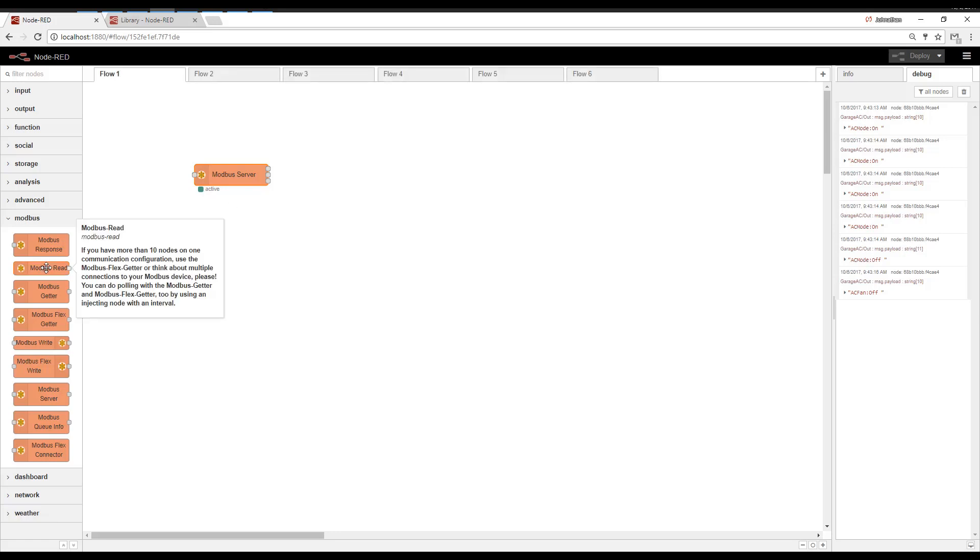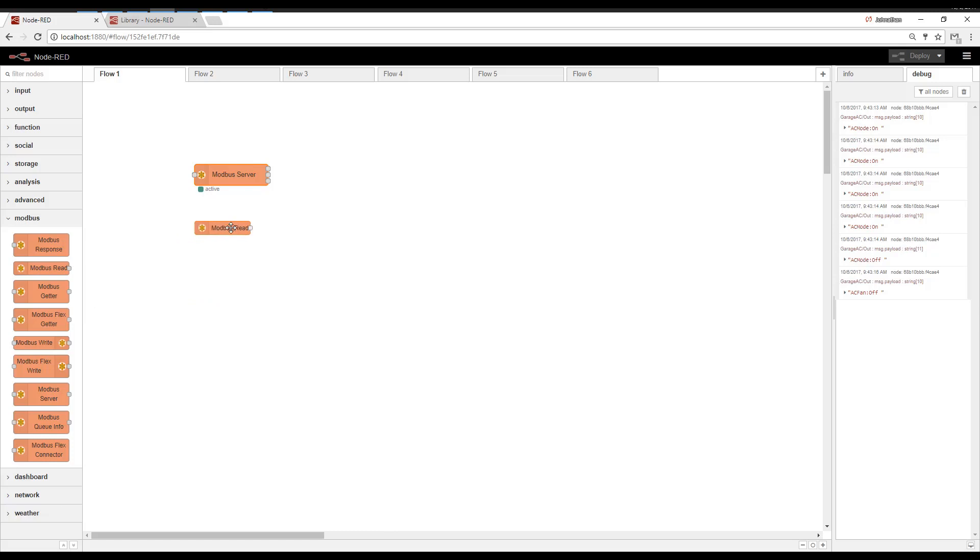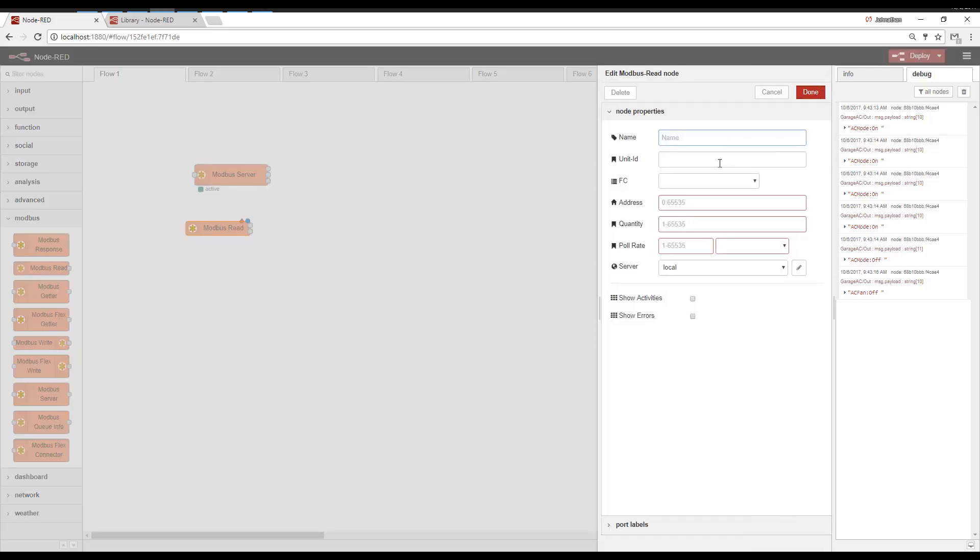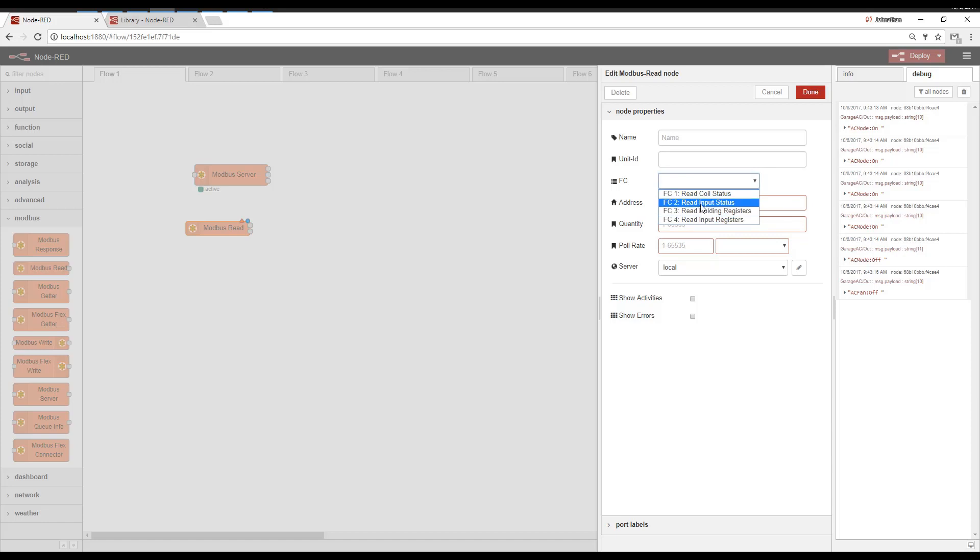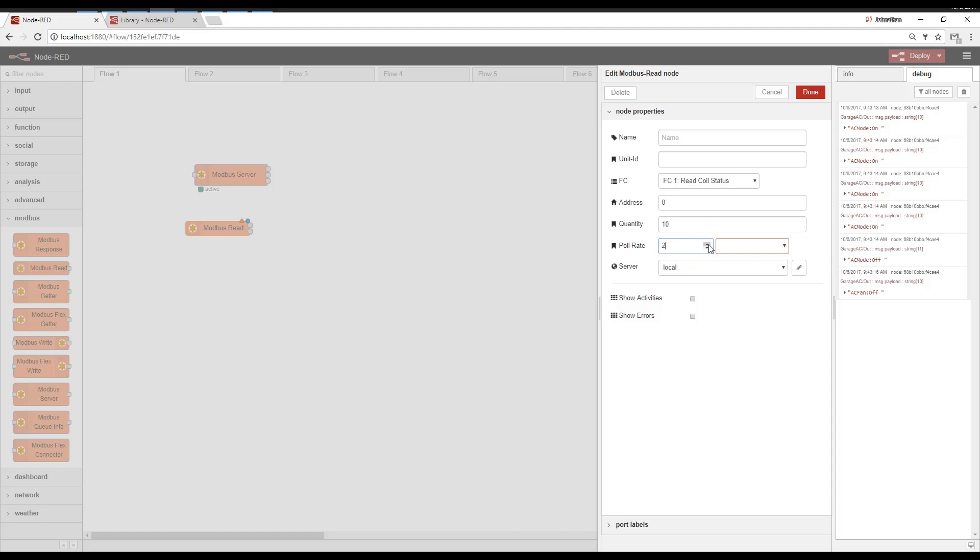And then the simplest way to make a Modbus Master is to do a Modbus Read. You can see here where we could type in the unit ID, the function code. So what do we want to read? Let's say a coil, address, and then how many of them. Then how often do we want to poll?